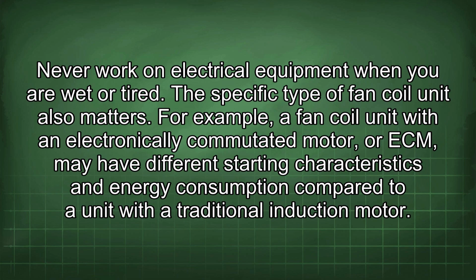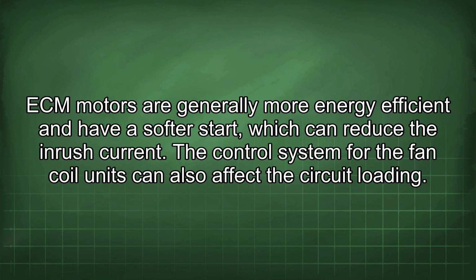The specific type of fan coil unit also matters. For example, a fan coil unit with an electronically commutated motor, or ECM, may have different starting characteristics and energy consumption compared to a unit with a traditional induction motor. ECM motors are generally more energy efficient and have a softer start, which can reduce the inrush current.